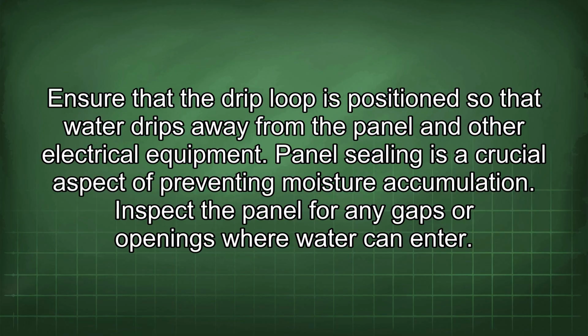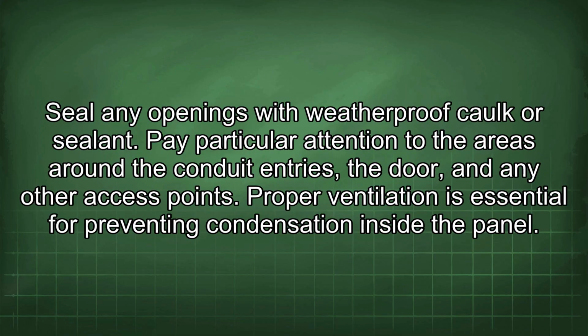Panel sealing is a crucial aspect of preventing moisture accumulation. Inspect the panel for any gaps or openings where water can enter. Seal any openings with weatherproof caulk or sealant. Pay particular attention to the areas around the conduit entries, the door, and any other access points.